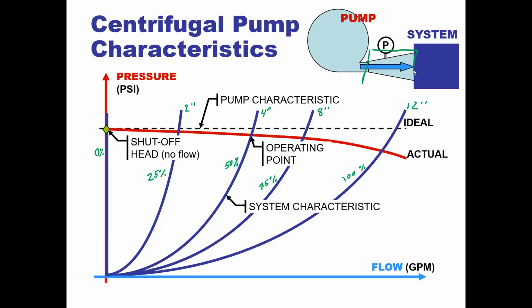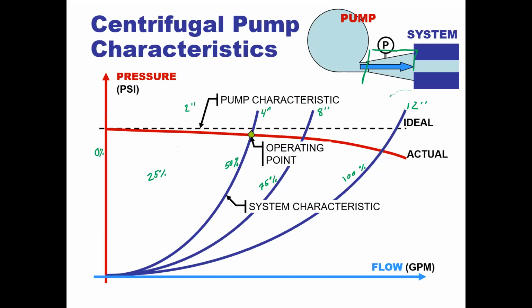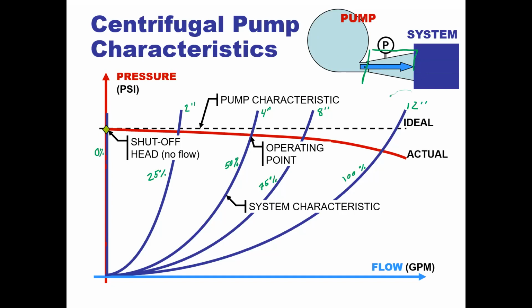Even though our system is closed off, there's still an area, there's still an area before that valve. So no more gallons per minute is going to be entering that area because we're at a zero flow scenario. So if you're asking what's going to happen to the pump if it stays running without a flow for 5 minutes, an hour, 2 hours, 2 days, it would overpressurize the system that's after the discharge of the pump, right? If it doesn't have an area to go into, then that portion of the system could overpressurize.